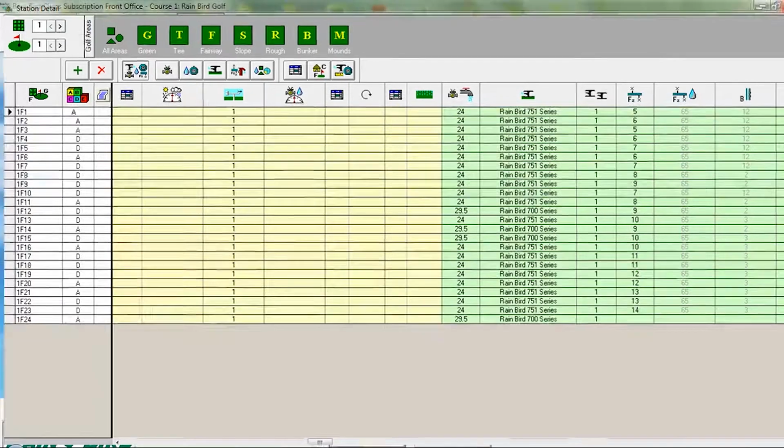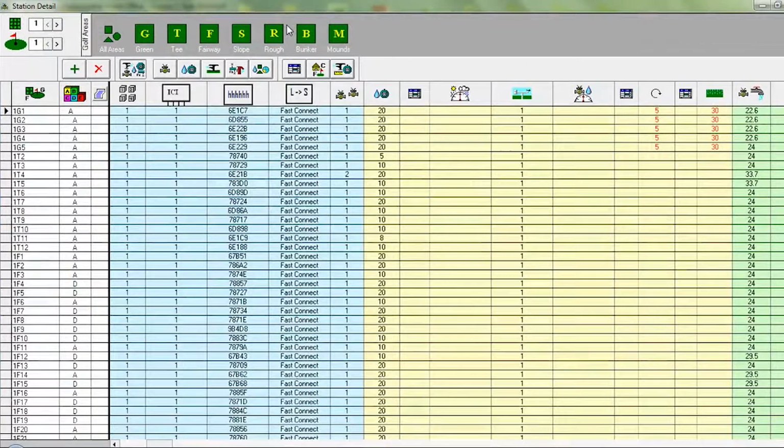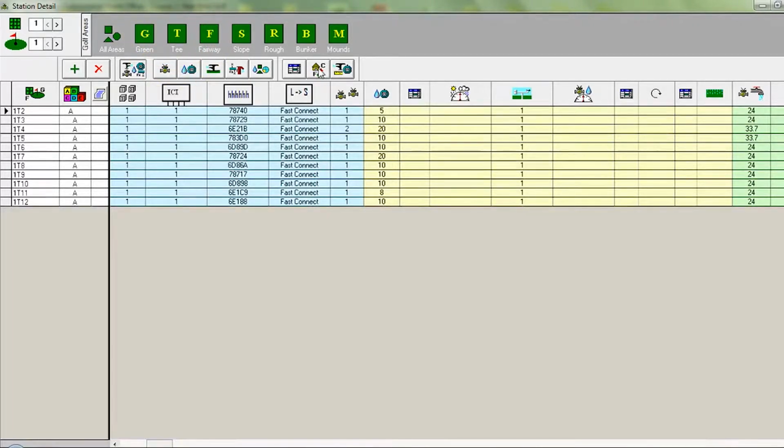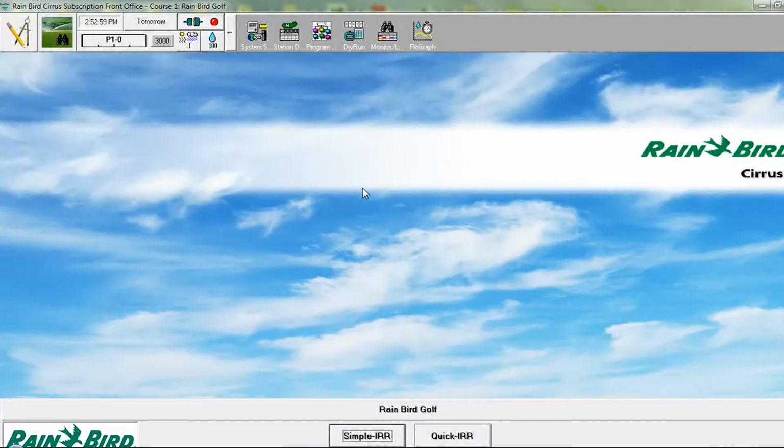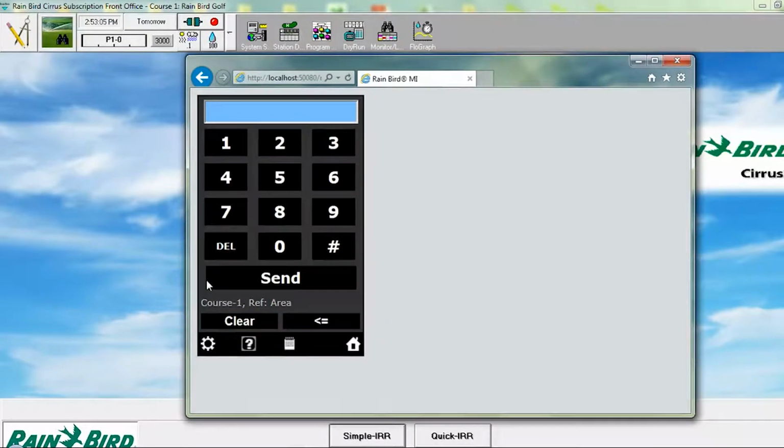Next, I will demonstrate extended command 32, which is device data. Device data is used to update the station attributes, such as number of valves. For this example, let's say we add twinned-up valves, which is 2 solenoids attached to one station output on T-head number 4. However, when we are out in the field and turn that station on, we determine it's actually not a twin station, but should only be one solenoid.